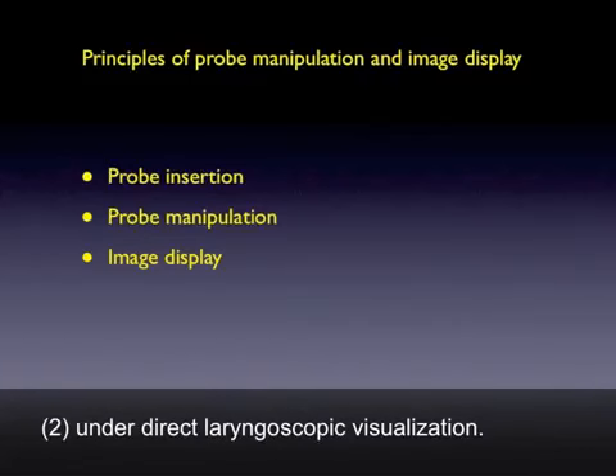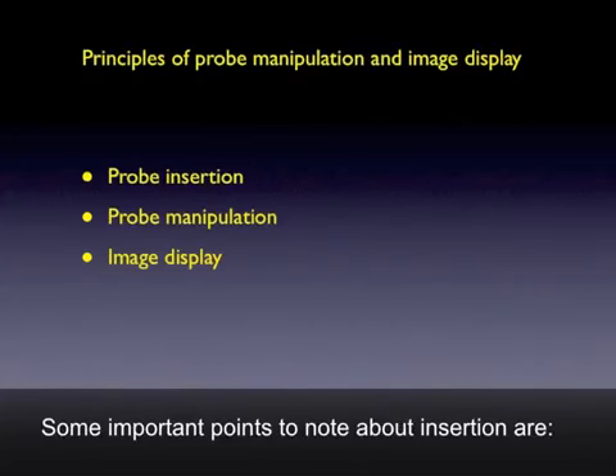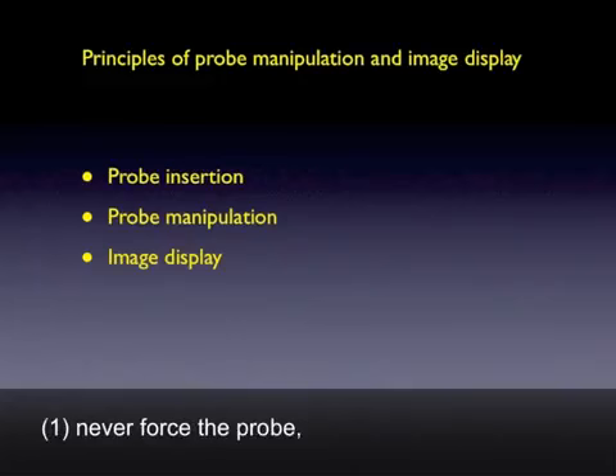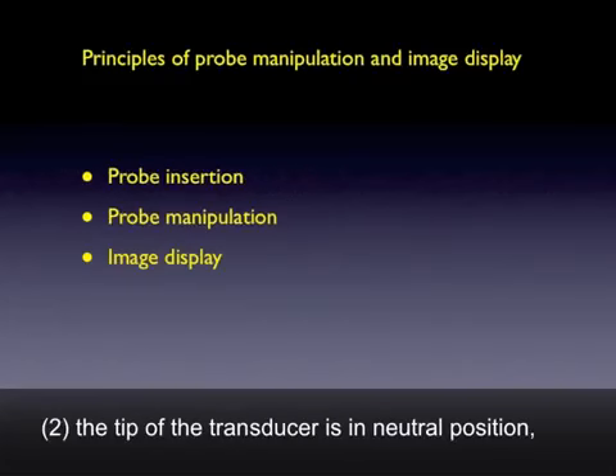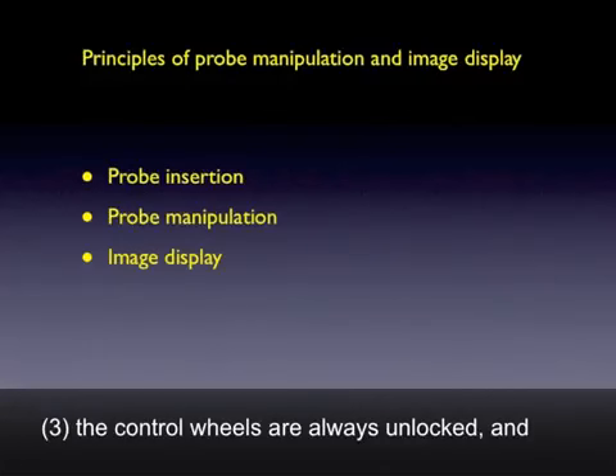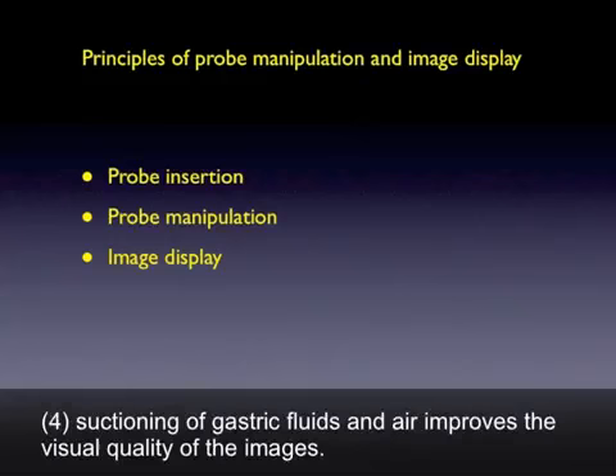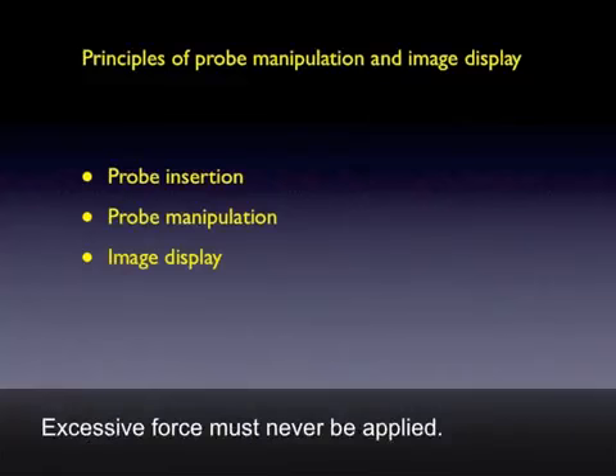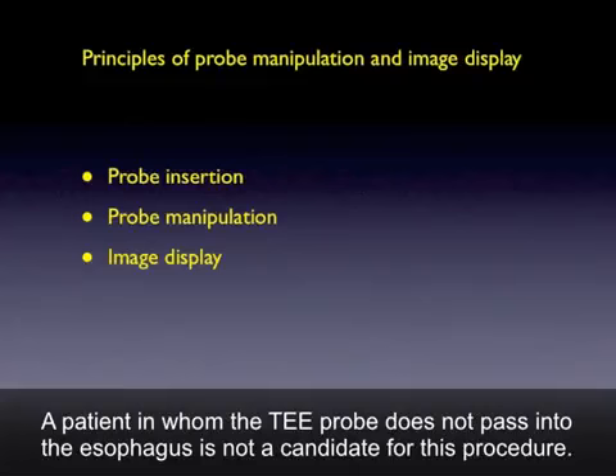Under direct laryngoscopic visualization. Some important points to note about insertion are: 1. Never force the probe. 2. The tip of the transducer is in neutral position. 3. The control wheels are always unlocked. And 4. Suctioning of gastric fluids and air improves the visual quality of the images. Excessive force must never be applied. A patient in whom the TEE probe does not pass into the esophagus is not a candidate for this procedure.